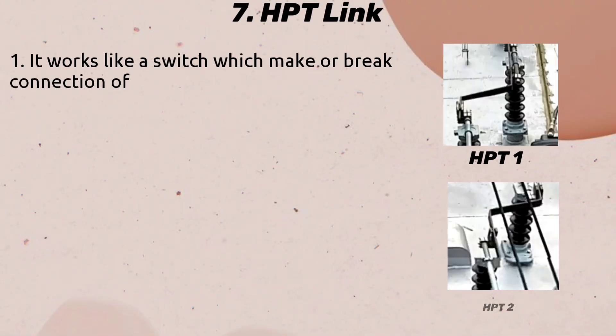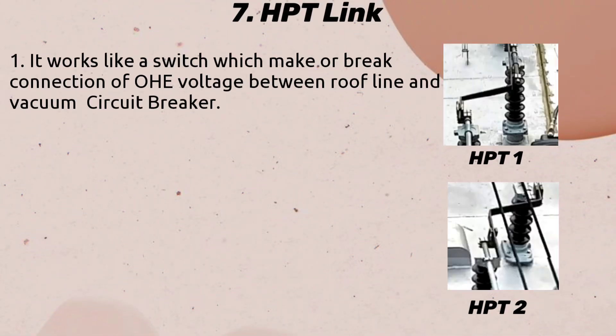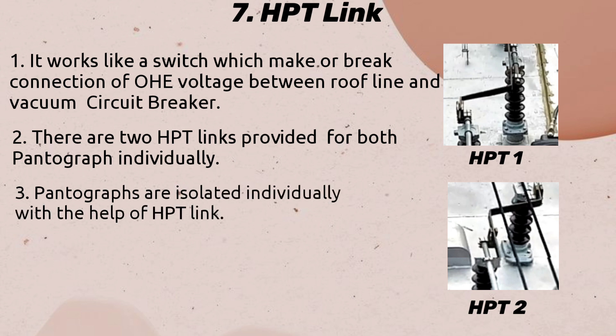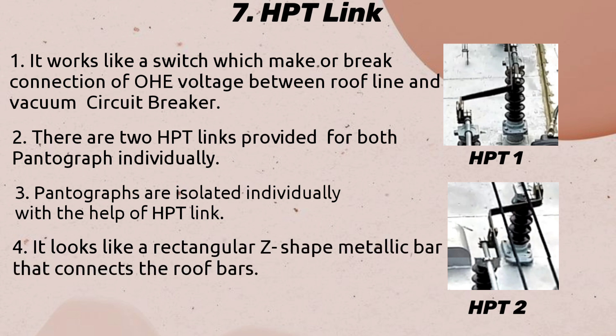HPT Link: It works like a switch which makes or breaks the connection of OHE voltage between the roof line and the vacuum circuit breaker. There are two HPT links provided for both pantographs individually. Pantographs are isolated individually with the help of the HPT link. It looks like a rectangular Z-shaped metallic bar that connects the roof bars.